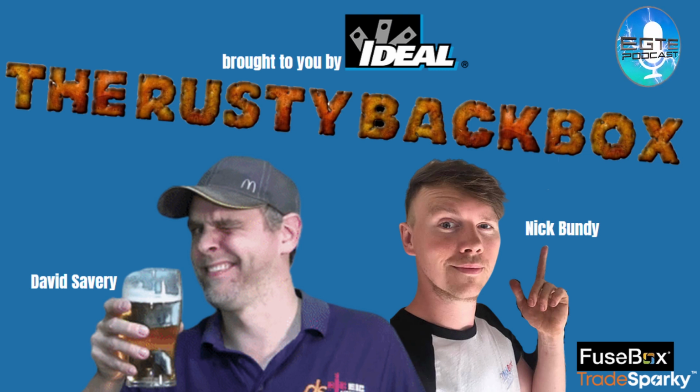Our consumer units are star breaker because there's no bus bar to lose. You lose the bus bar, the boards. What they used to do is strap it across line and neutral first, and then across breaker number 1. That was always fun when you turned it on if you weren't got your wits about you. So we have gone on and bought some Wylex ones now, because we found learners were going out into industry and just clipping the breakers onto the DIN rail and ignoring the bus bar because they'd never used one at college. So it didn't work as well as it could have worked.